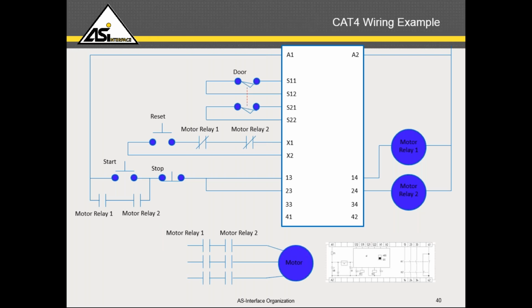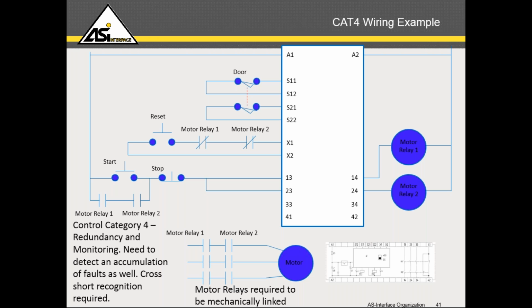Here is another real-life example that I would like to show you: the conventional way of wiring an interlocking switch or an emergency stop. Here we have a dual-channel circuit where we have the input channels, where it says door, connected to terminals S11, S12, S21, S22, and the contactors are connected with 13, 14, 23, 24, and then you have a feedback circuit for those contactors for any failure detection, with a reset button. This type of circuit is designed to monitor or detect any accumulation of faults, or a fault such as a cross short or short circuit in the input device or the output device.